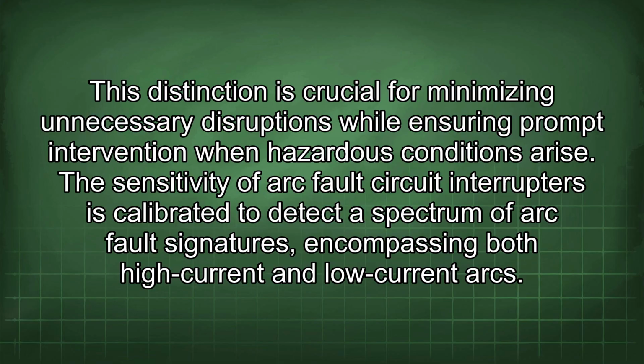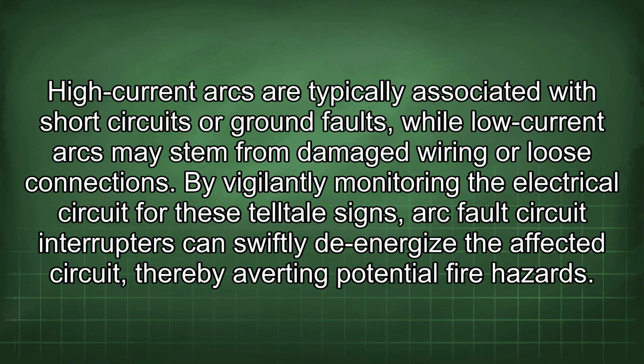The sensitivity of arc fault circuit interrupters is calibrated to detect a spectrum of arc fault signatures encompassing both high current and low current arcs. High current arcs are typically associated with short circuits or ground faults, while low current arcs may stem from damaged wiring or loose connections.